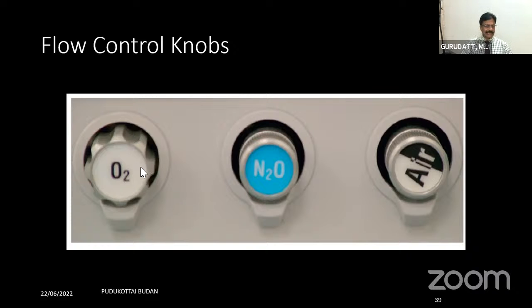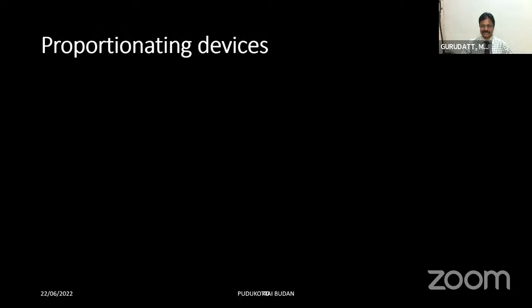You can see here the oxygen flow control knob is the largest one when compared to nitrous oxide and air, and it is cylindrical in shape, whereas these two are conical in shape. The third thing is the flutes, which are widely placed and large with oxygen. So even without seeing the flow control knob, you just touch it and you should know whether you are touching the oxygen or the other flow control knobs. Immediately after the flow control knobs, we have the proportionating devices. That's what I was talking to you about. The fail-safe valves are not actually fail-safe. That is the reason you require proportionating devices in the flow meter assembly.